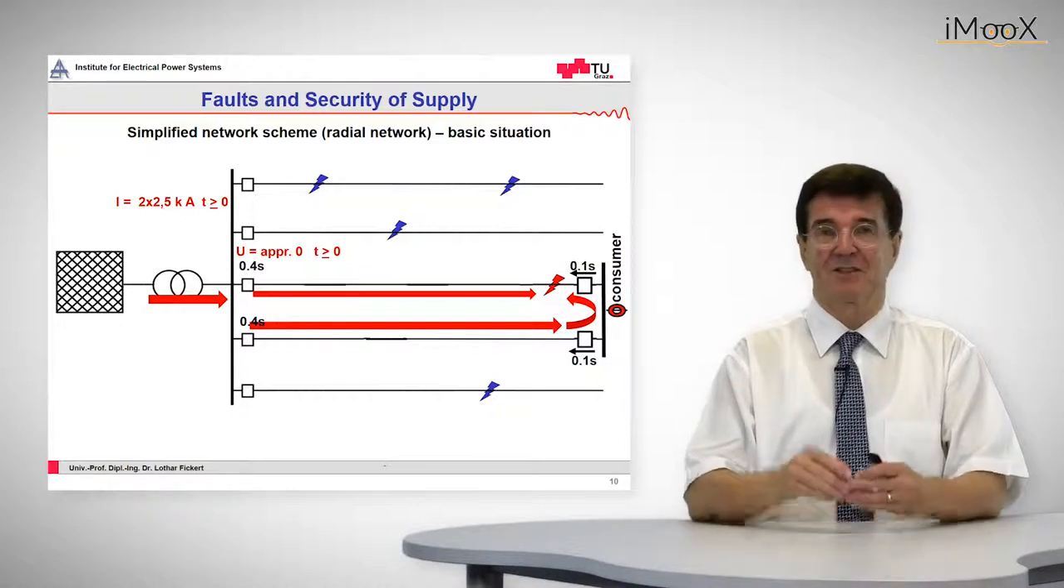So if now a fault occurs, we have the fault current of five kilo amps entering the medium voltage distribution network. It splits up into the two lines that feed into the fault. For example, if the fault is at the end of the line, then the fault current is split up 50 to 50 and we have 2.5 kilo amps flowing through each of those feeders.